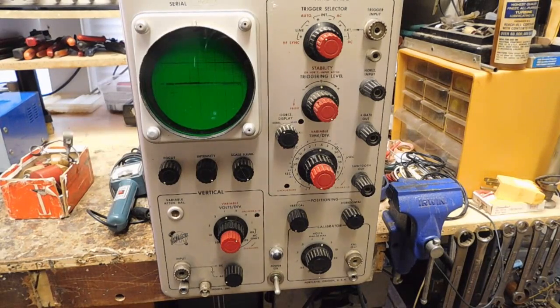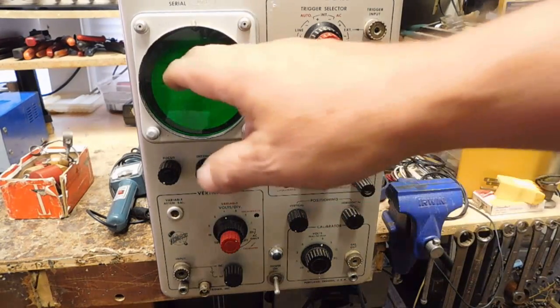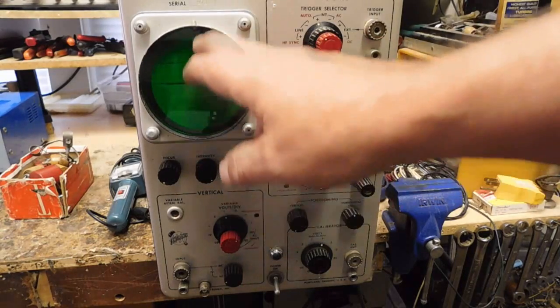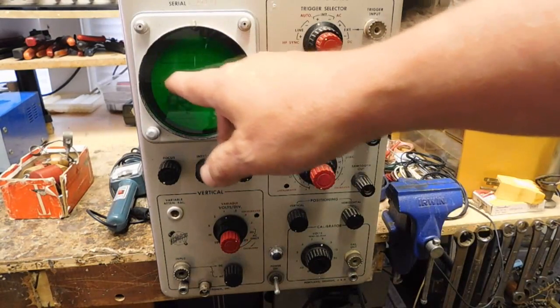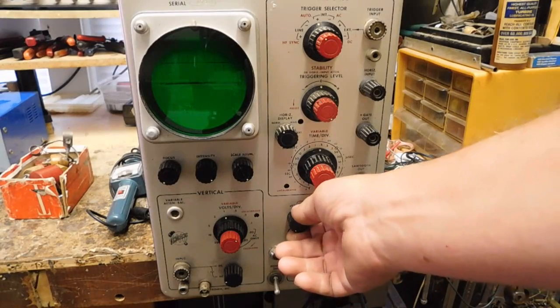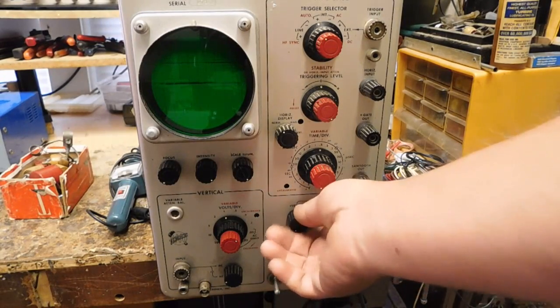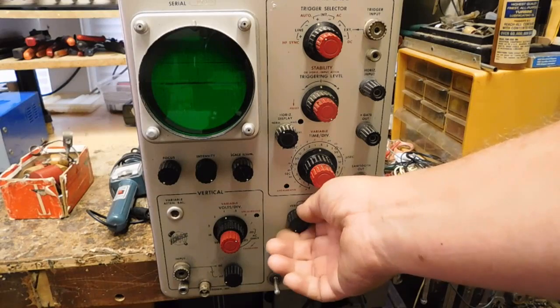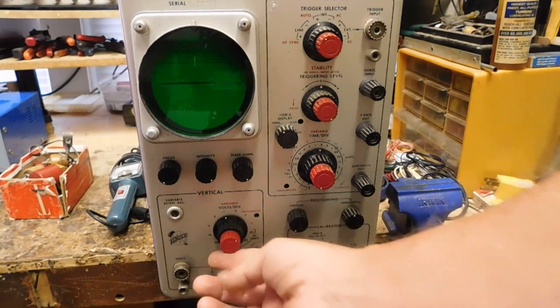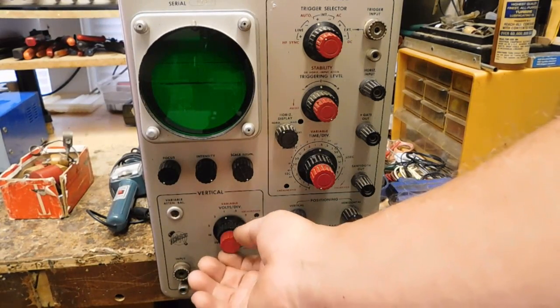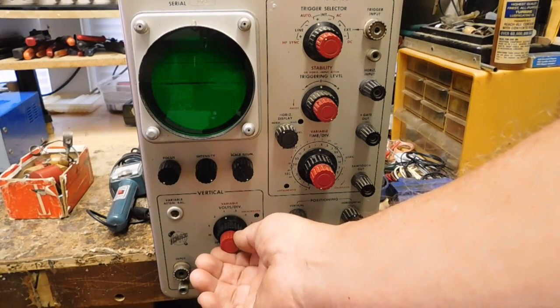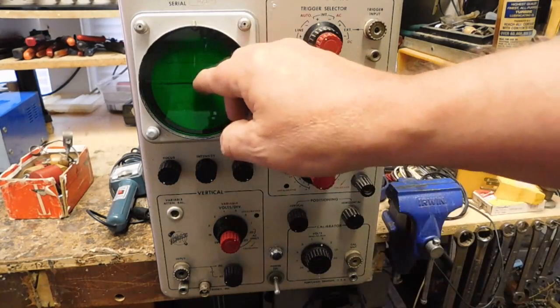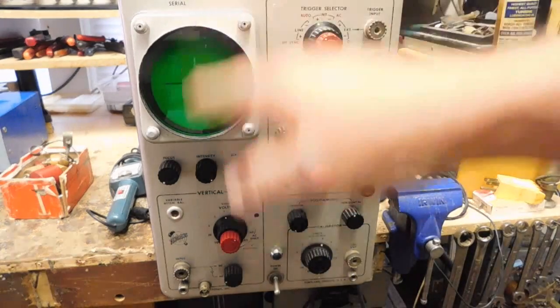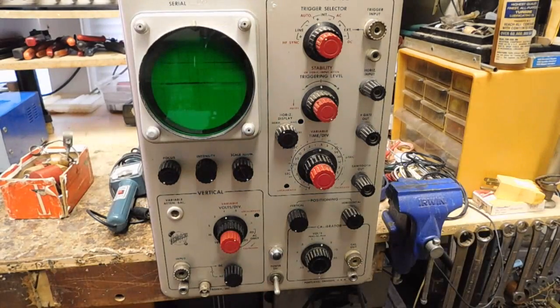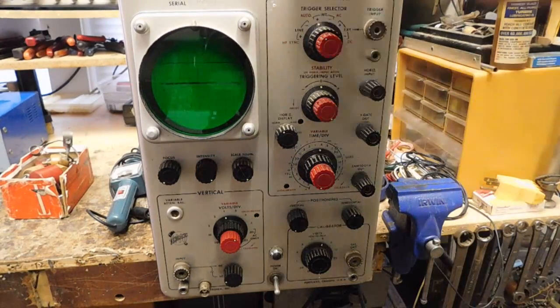Now the unit does have a few little problems. Trying to get the vertical to come down centered by adjusting the control down here, you have to turn it fully counterclockwise and then take the calibration and take it out of calibration on the vertical amp and move it some to even get it close to center. So there's an imbalance in there. So that'll be one troubleshooting thing that we'll go through when I get to this.